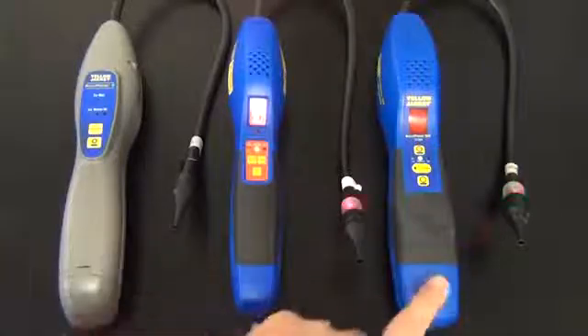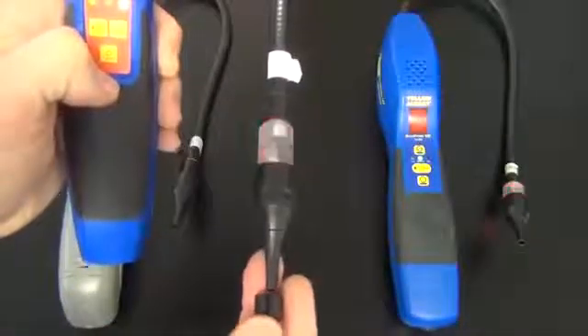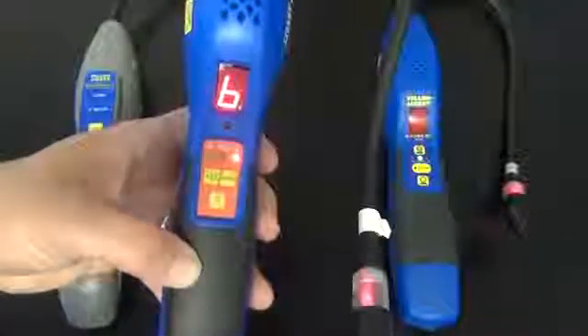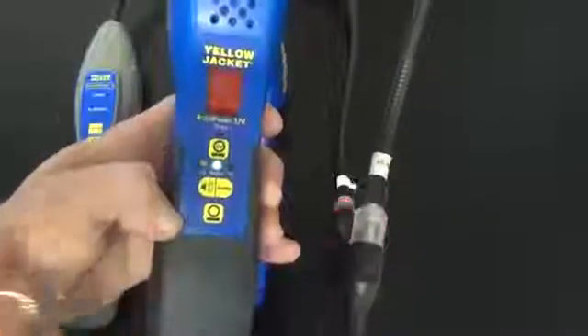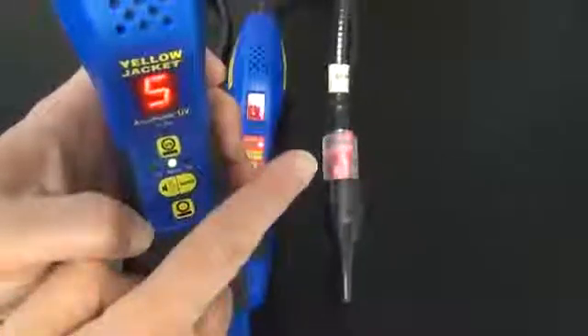On the original AccuProbe and the AccuProbe UV, you will get both an audible alarm and the light will flash, as well as the smart alarm. If you are using the mute and you do detection, you will get a number as well as the flash. On the AccuProbe UV, same thing — if you take it off mute, you will get an audible alarm as well as the flash. And if you have it on mute, you will get the smart alarm display as well as the flashing light.